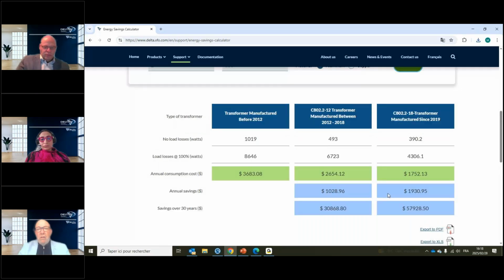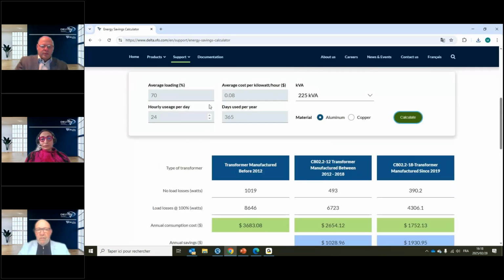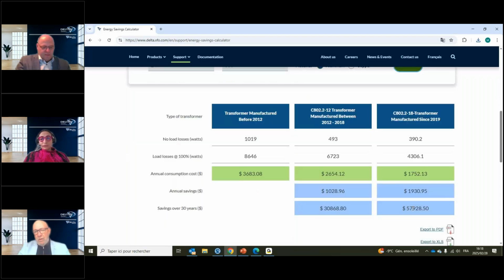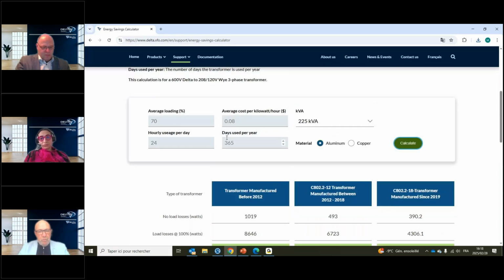So for a 225 kVA aluminum unit, at 70% load, which is probably the average load on a transformer, almost $58,000 of saving over the lifespan of the transformer. So that's a lot of money. So again, great tool. Just put in a few pieces of information, and it provides you all of the information. Just to give you a look of what the output looks like.